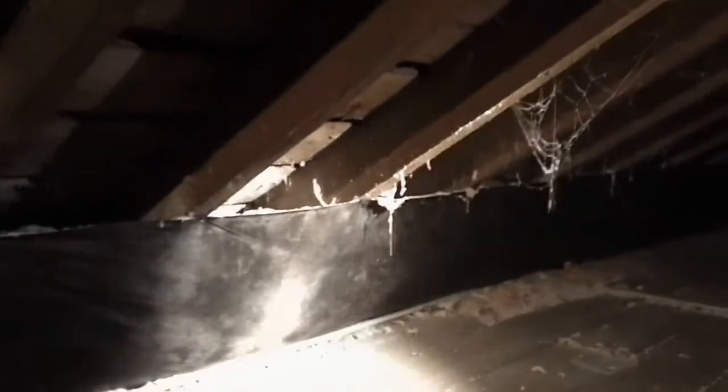We're in the attic, and I want to point a few things out. This house had insulation put in the attic floor. It's a cellulose insulation. You can see it's been dense packed underneath the floor. Also, insulation was added where the slanted ceilings are and where the rest of the flat ceiling is, where there's no wood floor. We have this material up to put insulation and hold it in place. That's a very good retrofit item.